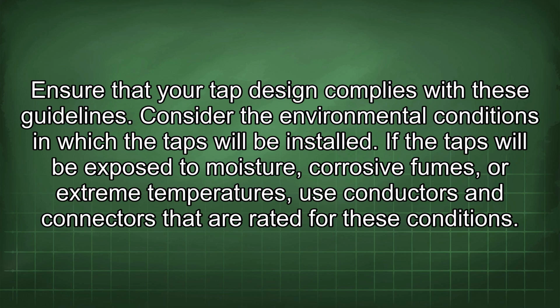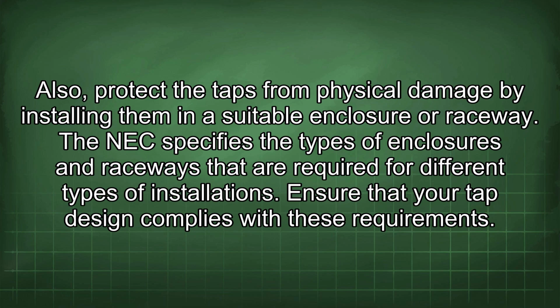Consider the environmental conditions in which the taps will be installed. If the taps will be exposed to moisture, corrosive fumes, or extreme temperatures, use conductors and connectors that are rated for these conditions. Also, protect the taps from physical damage by installing them in a suitable enclosure or raceway. The NEC specifies the types of enclosures and raceways that are required for different types of installations. Ensure that your tap design complies with these requirements.